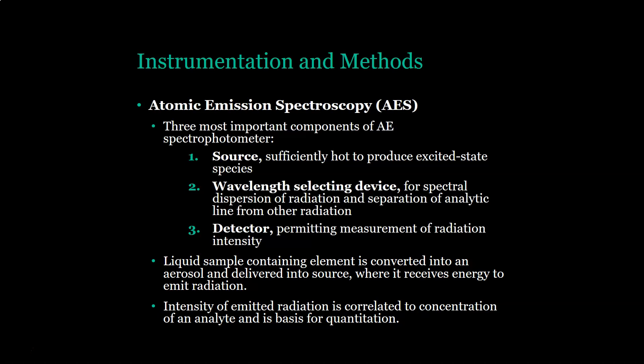A little bit about instrumentation and methods. The first is atomic emission spectroscopy. There are three important components of an AE spectrophotometer: the source, which must be sufficiently hot to produce an excited-state species of the metal; the wavelength-selecting device for spectral dispersion of radiation and separation of the analytic line from other radiation; and the detector that permits measurement of radiation intensity. The liquid sample is converted into an aerosol and delivered into the source where it emits radiation. The intensity of that emitted radiation is correlated to the concentration of the analyte — the more metal in the sample, the more intense the radiation.